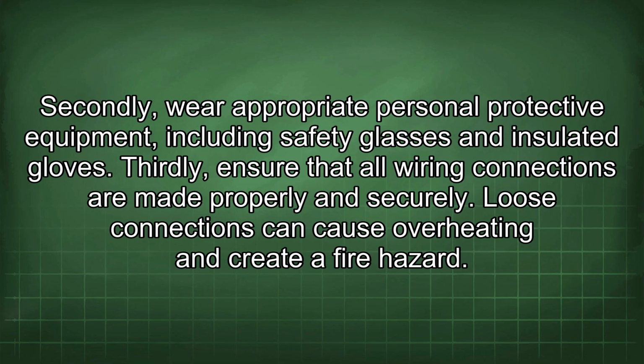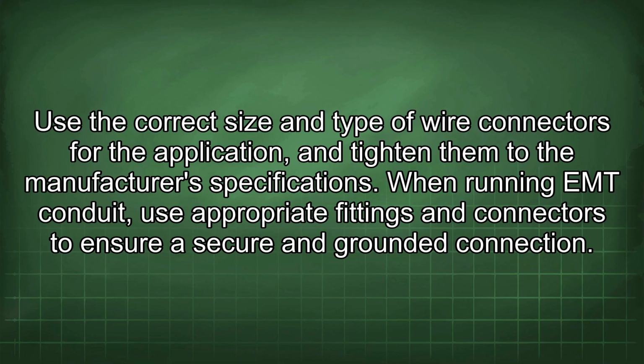Secondly, wear appropriate personal protective equipment, including safety glasses and insulated gloves. Thirdly, ensure that all wiring connections are made properly and securely. Loose connections can cause overheating and create a fire hazard. Use the correct size and type of wire connectors for the application and tighten them to the manufacturer's specifications. When running EMT conduit, use appropriate fittings and connectors to ensure a secure and grounded connection.